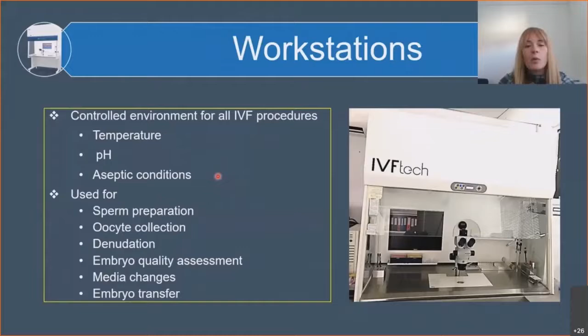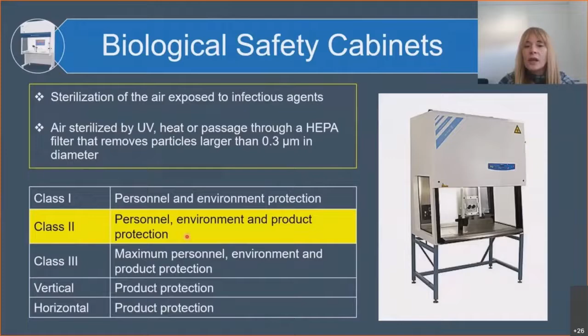It provides sterile conditions by sterilization of the air, either by UV heat or passes through a filter that removes the larger particles. If you want to choose between the different biological safety cabinets, keep in mind that the most recommended for an IVF lab is the Class 2 that provides personnel, environment and product protection.